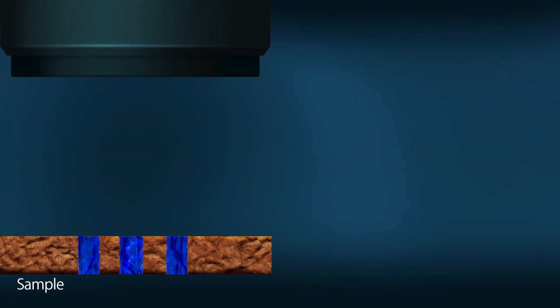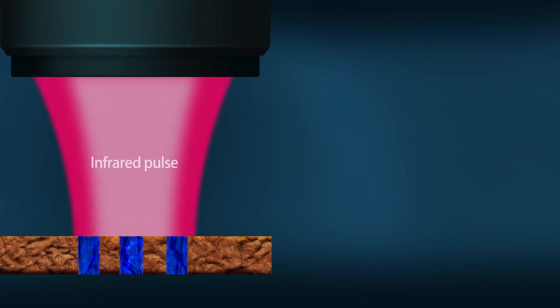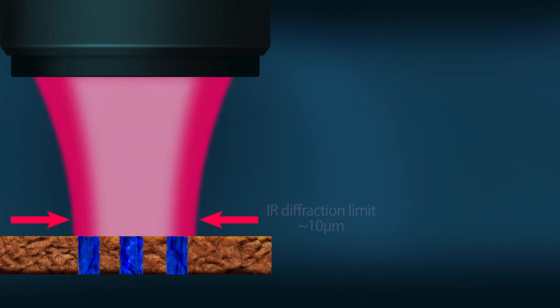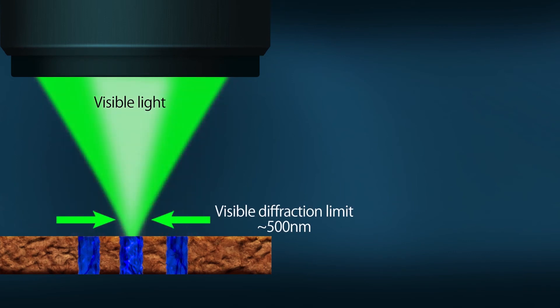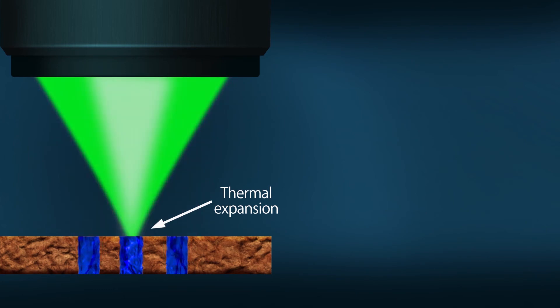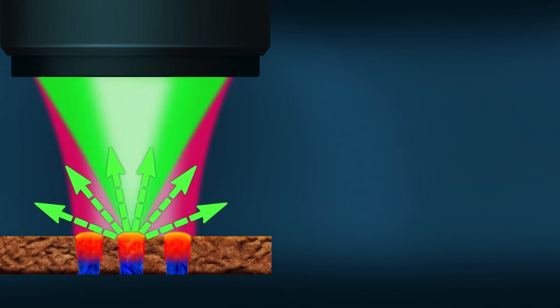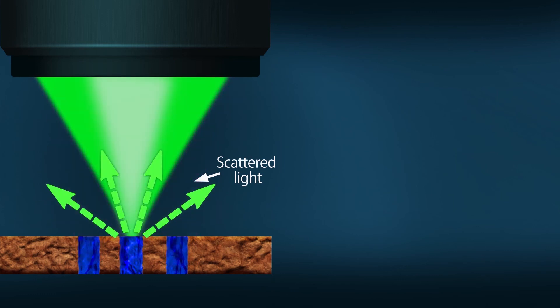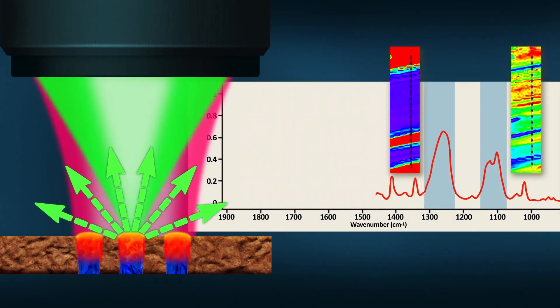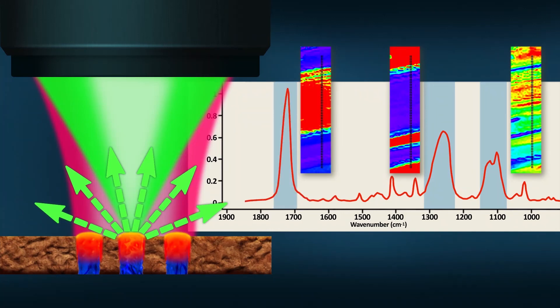It all starts with the microscope objective — a reflective Cassegrain style. Through that we shine a pulsed infrared laser beam, and being infrared it's fairly broad, maybe around 10 microns. At the same time we're shining in our probe beam, the green that's about 500 nanometers. The infrared generates thermal expansion, and that thermal expansion changes the way the green light is reflected or scattered back. So as we're tuning our infrared laser from one wavelength to another, we monitor the intensity of the green light reflected back, and from that we calculate out what is essentially a pure infrared spectrum collected in reflection mode.